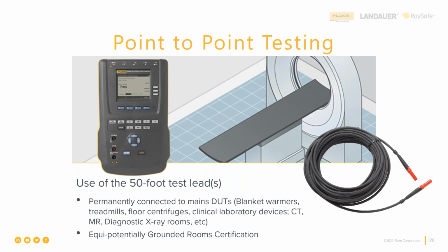Point-to-point testing can be referenced to protective earth or ground, or sometimes, on equipment permanently connected to mains power, you cannot break into that mains power connection. So you're going to get close even if you're not right on ground, and therefore your reference point will be the reference point you choose. The measurement you make with the red test lead is going to be whatever that is, current or voltage, with respect to that reference point you chose, because you could not get on the ground. Point-to-point testing is the way to do it. We can measure volts, ohms, and microamperes or milliamperes using this mode of testing.